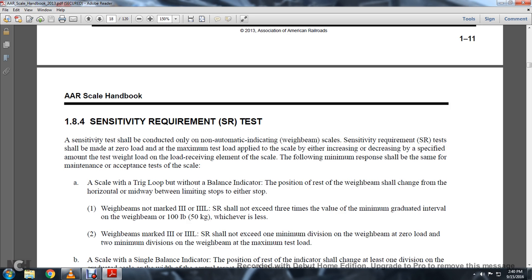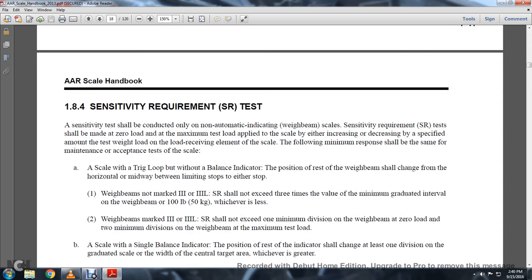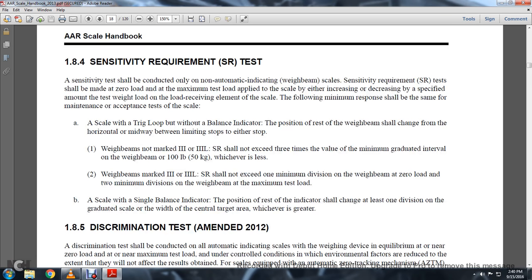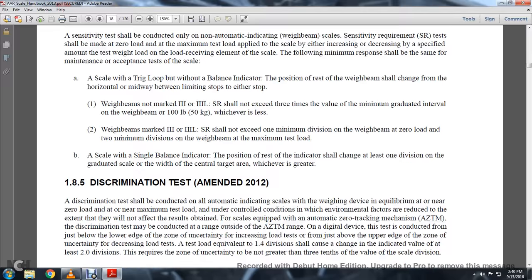Weight beams not marked with the 3L sensitivity requirement shall not exceed three times the value of the minimum graduated interval of the weight beam, or 100 pounds, whichever is less. Weight beams marked 3 and 3L: the sensitivity requirement shall not exceed one minimum division of weight beam at zero load, and two minimum divisions of weight beam at maximum test load. A scale with a single balance indicator: the position of the indicator shall change the length of one division on the graduated scale, or the width of the central target area, whichever is greater.